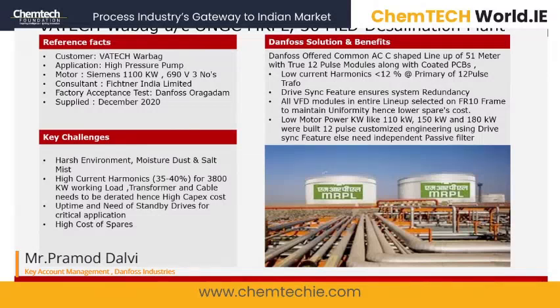Then what Danfoss has done is we have done all this lineup in one frame of the module, so that the end user can keep the lower spares. So we have done the modular construction. It will come in a subsequent slide. All the low power ratings, like 110 kilowatt, 150 kilowatt and 180 kilowatt, were built in the 12 pulse customized engineering. So there is no need for additional filters for the low rating drives.